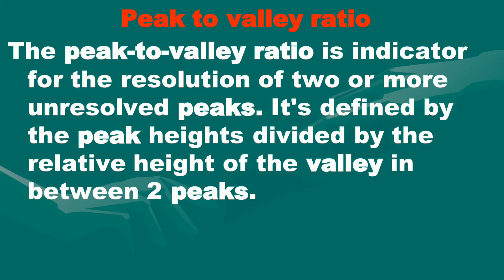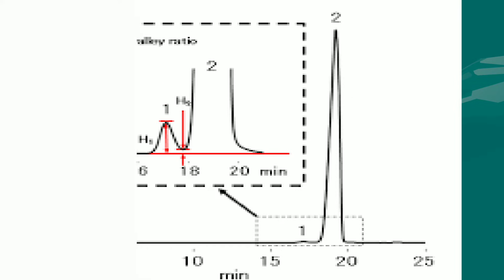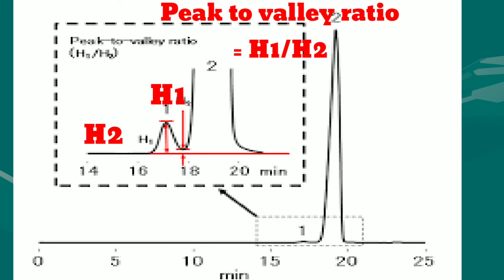Next is peak to valley ratio. The peak to valley ratio is an indicator for the resolution of two or more unresolved peaks. It is defined by the peak height divided by the relative height of the valley in between two peaks. In this figure, you can see how to calculate the peak to valley ratio between two peaks. The formula of peak to valley ratio is H1 / H2.